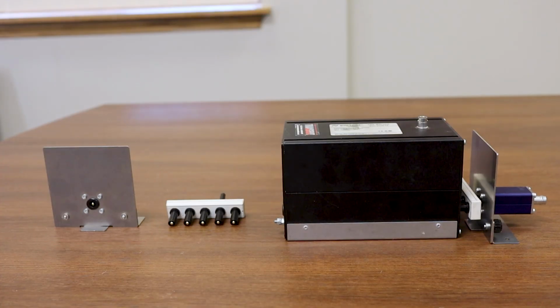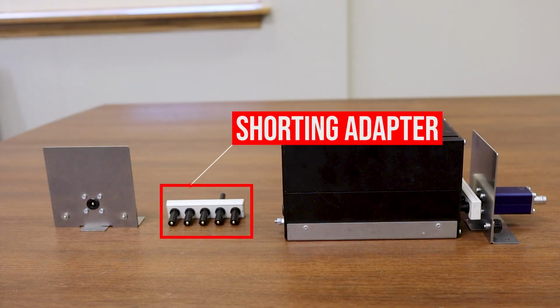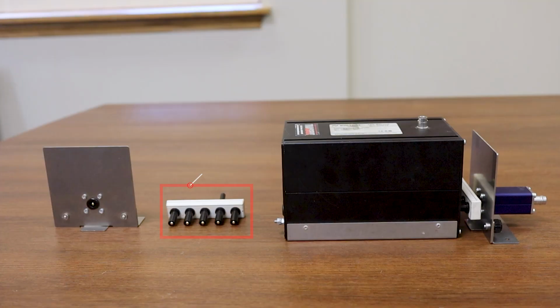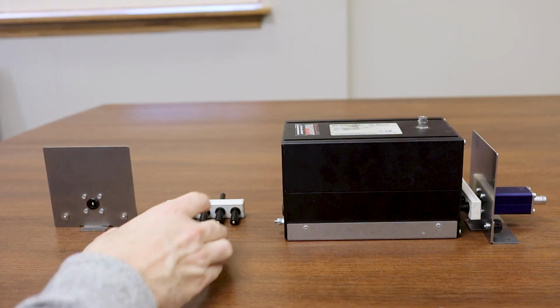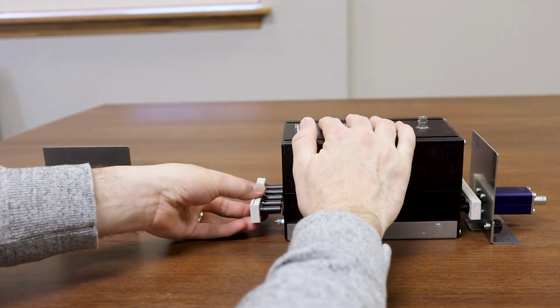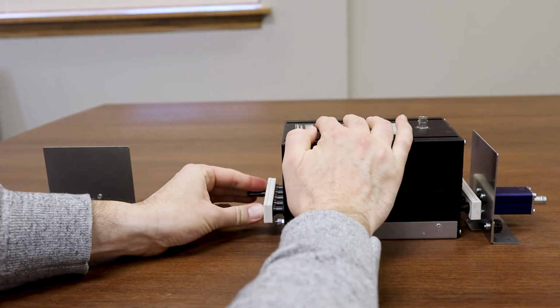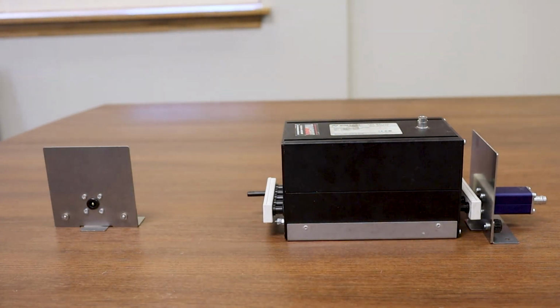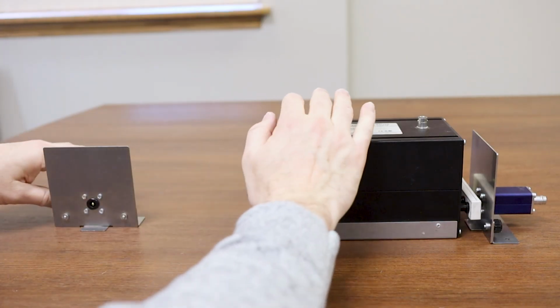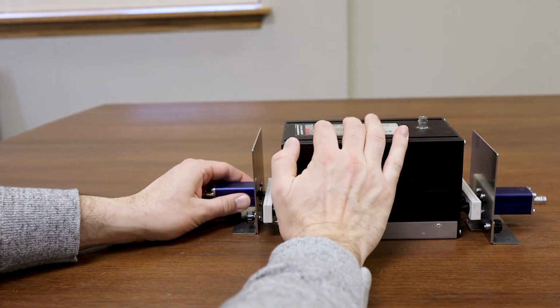This has a connection on one side which will go to our shorting adapter and a BNC connection on the other. Next to that we have our shorting adapter, and it's designed for the associated CDN and should be ordered along with the CDN and the 50 to 150 ohm adapter. When we're conducting the calibration, we'll slide our shorting adapter in the slots, just like that. Next, we'll put our 50 to 150 ohm adapter connected right there.